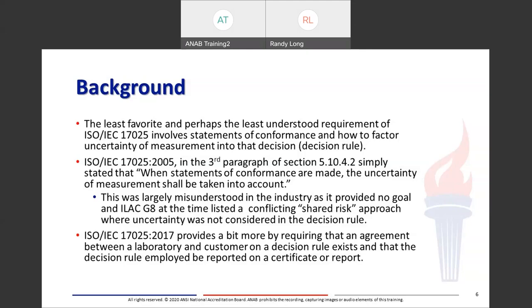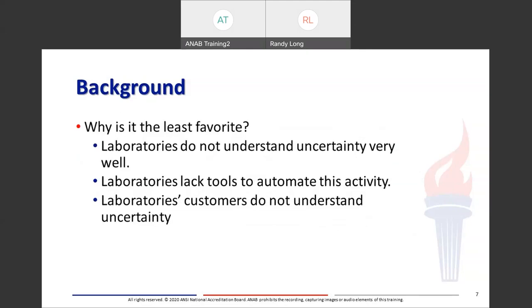17025:2017 provides a bit more by requiring that an agreement between the laboratory and customer on a decision rule exists, and that the decision rule employed be reported on the certificate or report. Why is it the least favorite? Laboratories don't understand uncertainty very well, they lack tools to automate the activity, and customers often don't understand uncertainty themselves.